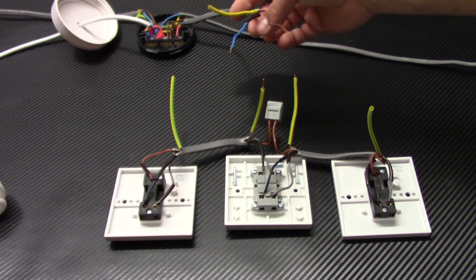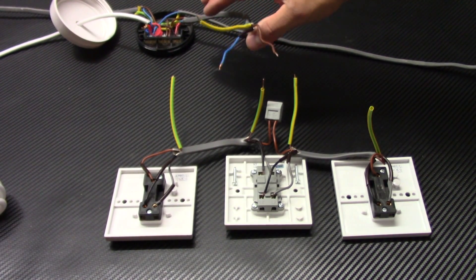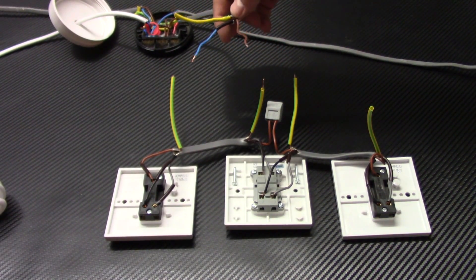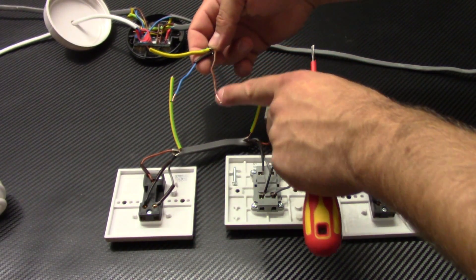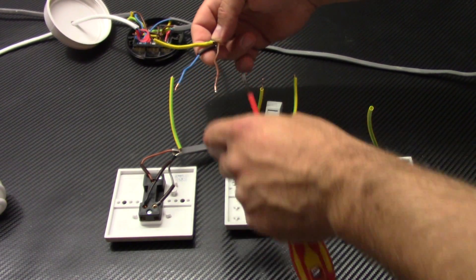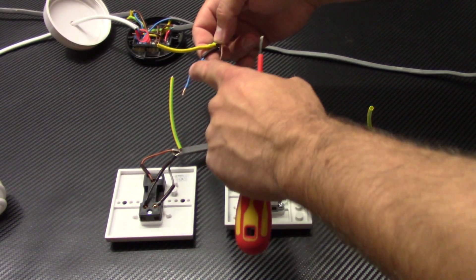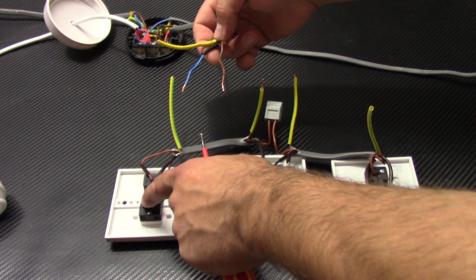So now it's time to connect this cable coming from the ceiling rose. We connect it to the two-way switch to the first one. This is our live wire. So we connect it to L2. And this is our switch live. We connect it to L1.